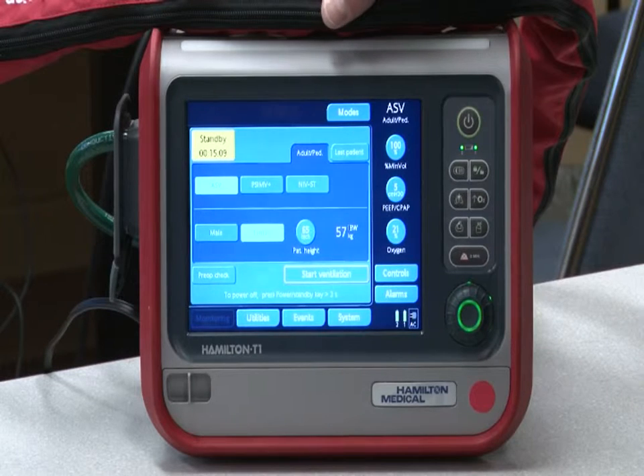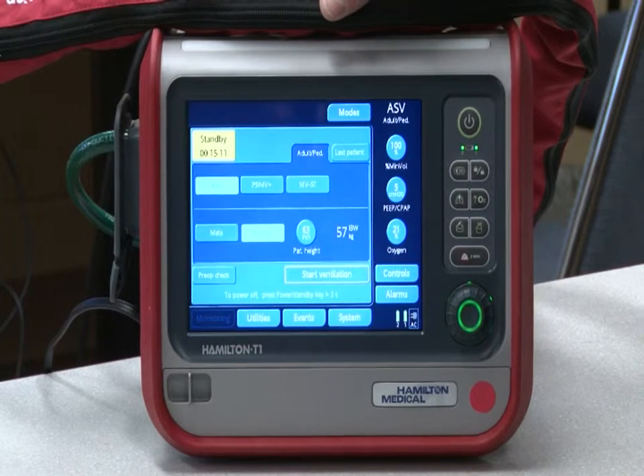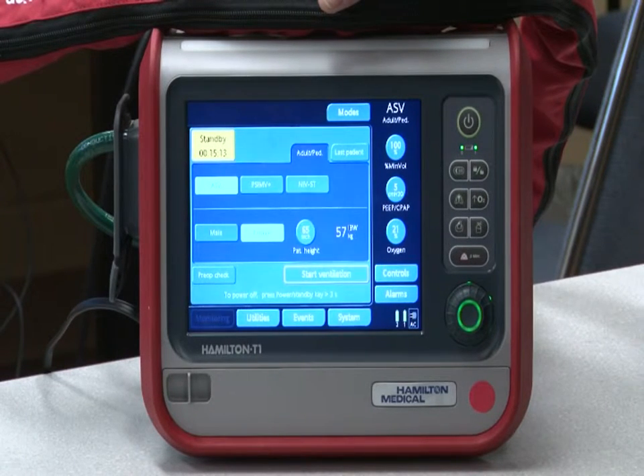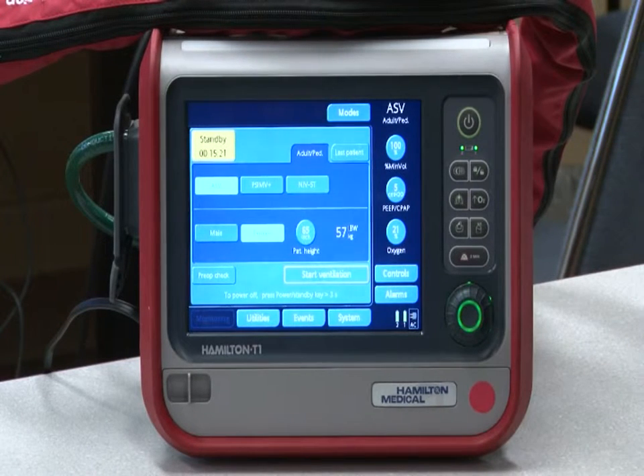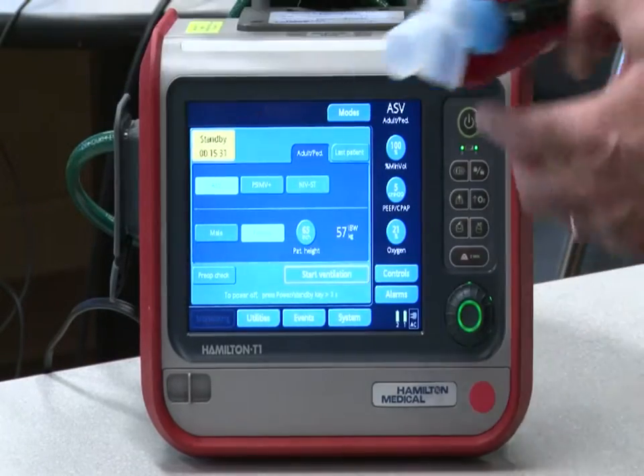And what that loud noise is, these ventilators are capable of a very high flow rate, about 260 liters a minute. So what you're going to hear is 260 liters a minute of flow coming out of the end of that circuit. When it starts to get really noisy, we're going to cap the end of it and hold it capped until the screen changes back and gives you a little check mark and a date and a time stamp. So I'll do mine first to show you.